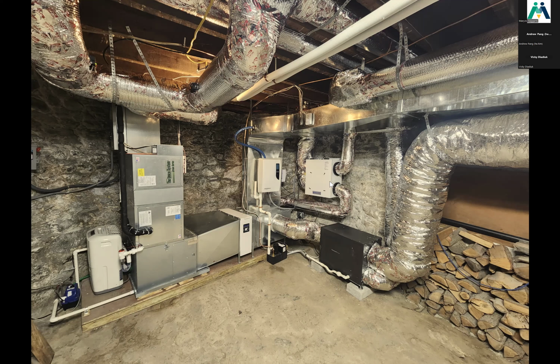But the equipment we use also includes an all-house dehumidifier system running in conjunction with the AC unit. Therefore, it can dry out the air in the summer, instead of running the air conditioning full blast to try to dry out the air. We're using the all-house dehumidifier to dry the air out, and then we distribute that cooler air around the house. This setup also required a whole house humidifier in the winter, because they had requirements for proper humidity levels in the building.